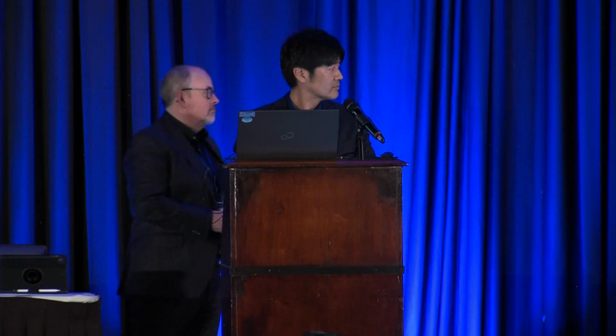Yeah. The calorific value, and how you went from individual sound. It's a kind of calculation. The optical sensor itself measures the refractive index directly, and the sonic sensor measures the sound speed. Then we calculate from the measuring results and output the calculated value on the display. Okay. Sorry. There's a different slide in a different slide deck that shows the calculations for the optical bench and the calculations for the sonic bench, and they basically solve simultaneous equations to develop a constant for the non-BTU contributing components. So that's how they were able to be on that one line. Right, right.